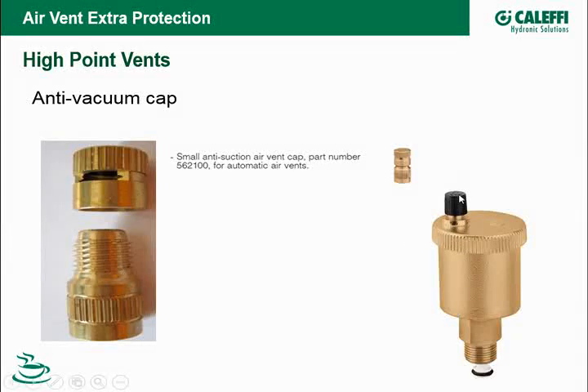Well, you can actually suck air into an air vent. This little float that's in there, if you've got a condition where you're pulling the pressure to a negative on this, air can actually come in this vent. And you're going to see this specifically on systems that have high head pumps that are pumping towards the expansion tank. So every time that circulator kicks on, there's a little droop or drop in pressure on the suction side of it. If you happen to have one of these vents in the system somewhere, it could be on a radiant manifold, it could be at the high point in an air handler. A lot of these vents are installed in systems for high point air elimination. They can actually allow air to come in.